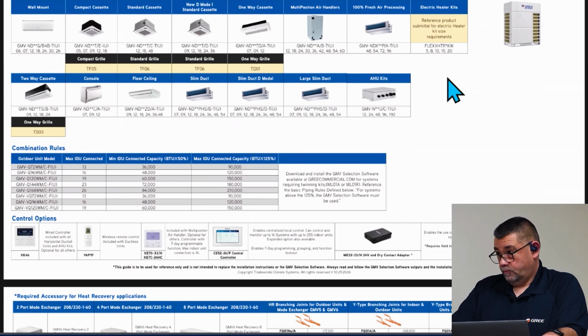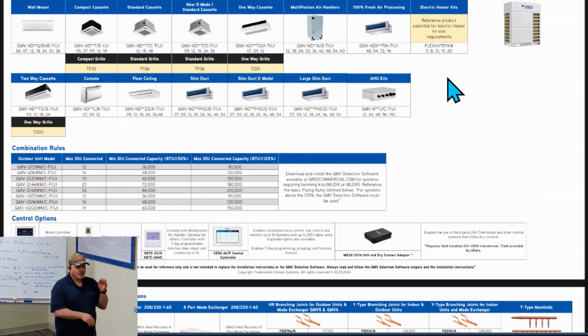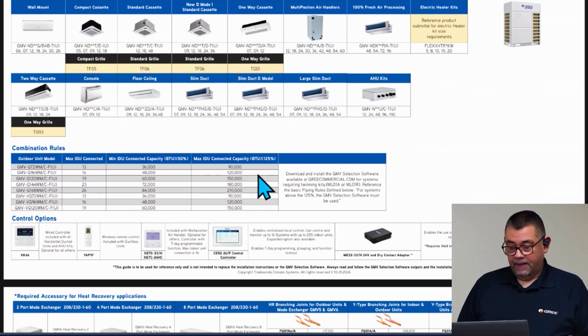If you've got, say, 3 indoor units, and one of those units goes down, as long as we maintain 50% connected capacity or higher, the other 2 units can stay functional. If we fall below that 50%, nothing runs. See, this is what separates us from some of the other brands, because if you lose one of their indoor units, the whole system shuts down. Right? And then the other thing we're pointing out here is the maximum connected capacity.